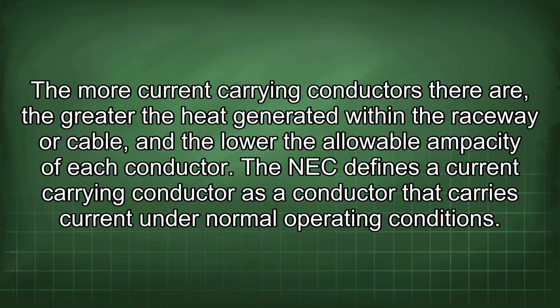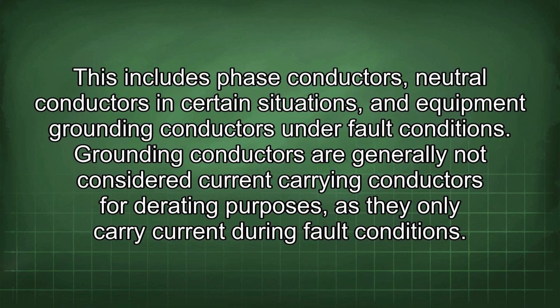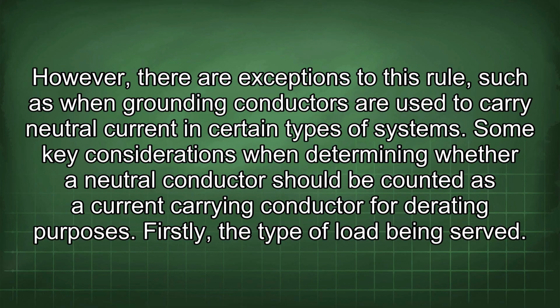The NEC defines a current-carrying conductor as a conductor that carries current under normal operating conditions. This includes phase conductors, neutral conductors in certain situations, and equipment grounding conductors under fault conditions. Grounding conductors are generally not considered current-carrying conductors for derating purposes, as they only carry current during fault conditions. However, there are exceptions to this rule, such as when grounding conductors are used to carry neutral current in certain types of systems.